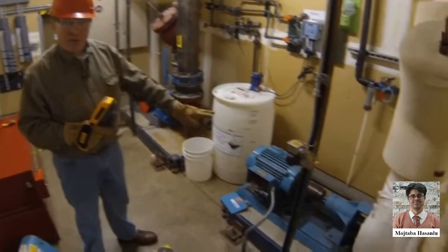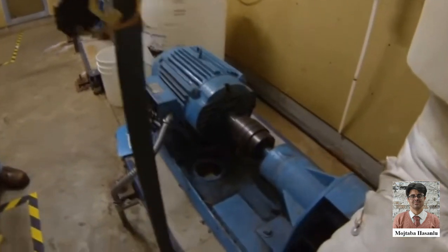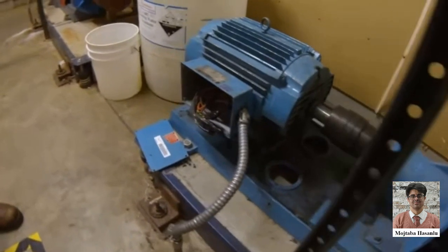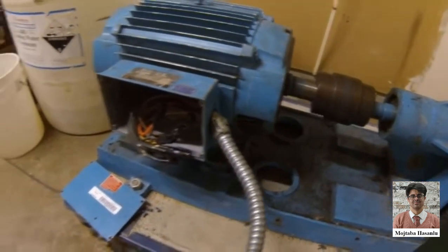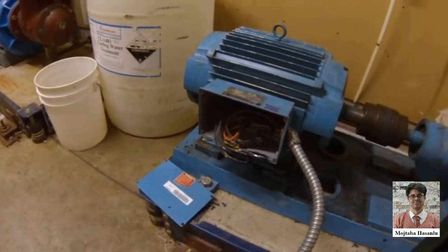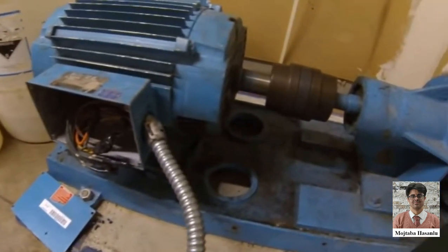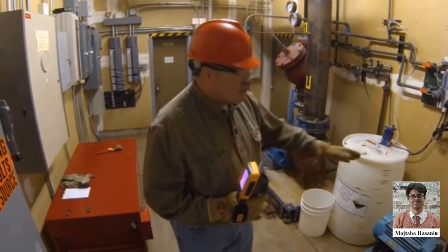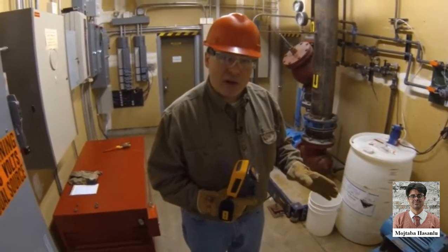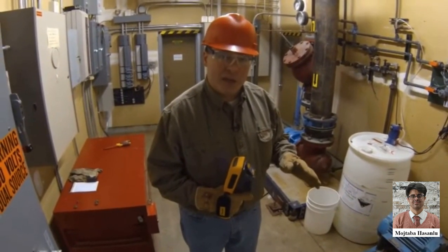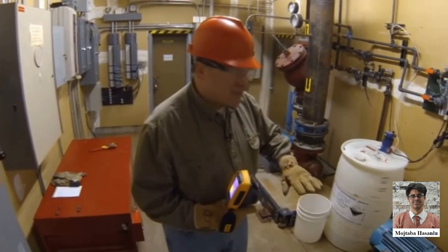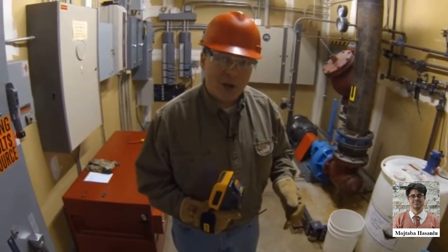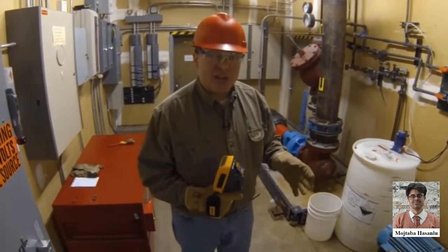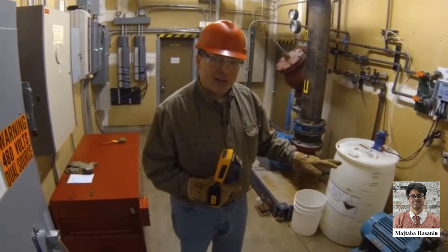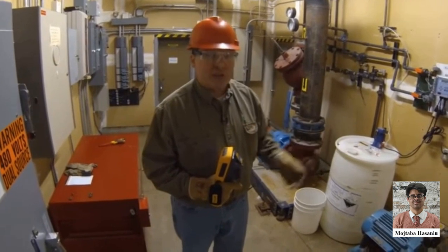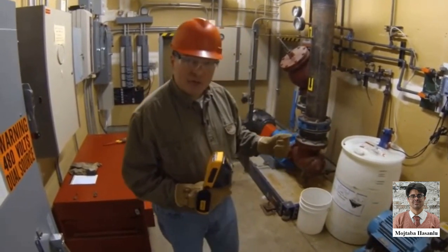Here we have an electrical motor coupled to a pump. The work that we've done in advance, obviously you can see that we've removed the shroud over the coupling and we've removed the cover over the junction box or the termination box. You need to have direct line of sight with thermal imaging in order to do a proper inspection. The first thing that I generally like to do is take a look at the overall motor housing itself, and I'll be looking for unusual or localized hotspots that I wouldn't expect. In a normally operating motor, you would expect nice even heating and distribution across the entire housing of the motor. If you see anything that's off, that could be indicative of a problem. Likewise, if this motor is running a lot hotter altogether over the entire motor housing, that's an issue as well. So let's take a look first and see what we find out.